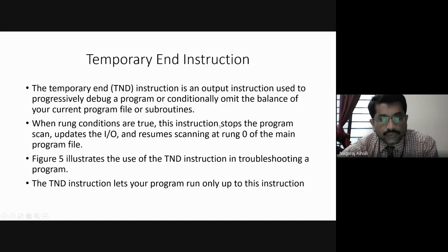When rung conditions are true, the instruction stops the program, scans it, updates the IO, and resumes scanning at rung 0 of the main program file. Look here, students. It resumes scanning at rung 0 of the main program file after the end instruction has been executed. Figure 5 illustrates the use of the TND instruction in troubleshooting a program.